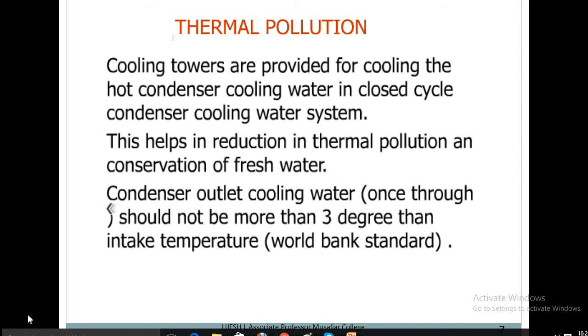Thermal pollution: Cooling towers are provided for cooling the hot condenser cooling water in a closed cycle condenser cooling water system. This helps in reduction of thermal pollution and conservation of fresh water. The condenser outlet cooled water temperature should not be more than 3 degrees above the intake temperature. A cooling tower is a heat rejection device that rejects waste heat into the atmosphere, normally used to cool water by direct contact between water and air.